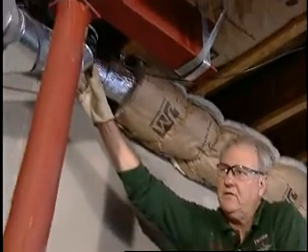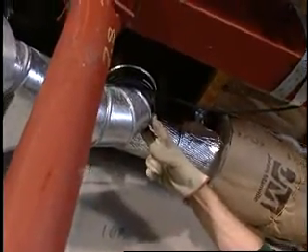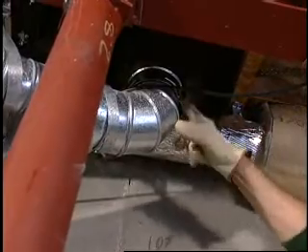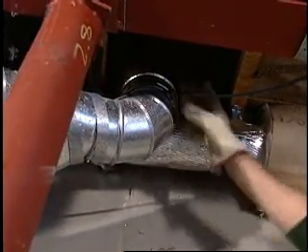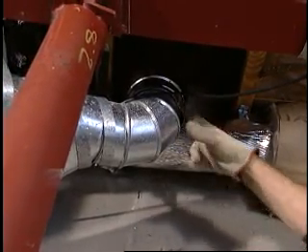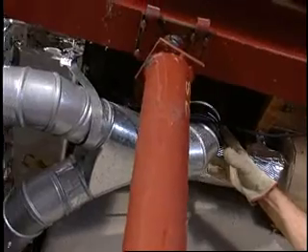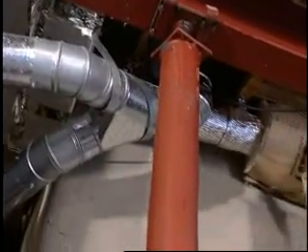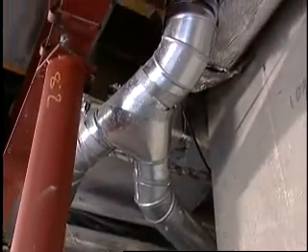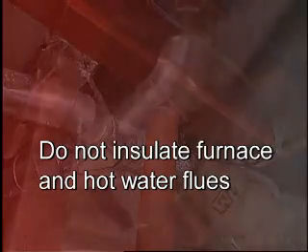Right over here, behind this structural pole, we have the furnace flue — this is where the exhaust is coming out of our furnace and water heater. You'll notice this is a triple wall pipe, what we call a vented pipe that the flue goes through, running all the way up through the first floor and attic. This triple wall adds air in between, ventilating it so you don't have direct heat against anything. I really don't want to put kraft paper directly next to it, so I used the duct wrap material on that section of ductwork going to this portion. Remember, we will never insulate this hot flue.